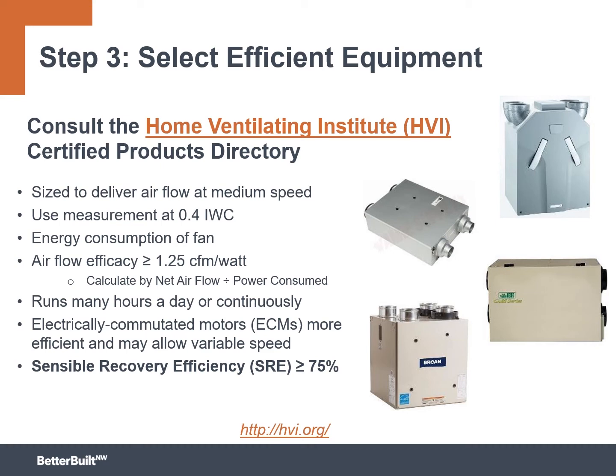As we've gone through all of these efforts to make our home more efficient, we want to run many hours a day or continuously, which is ideal, again, to keep us from having to supersize our heat recovery ventilators. We want to make sure that the equipment we choose uses electrically commutated motors, or ECMs. They're much more efficient and may allow for variable speed.